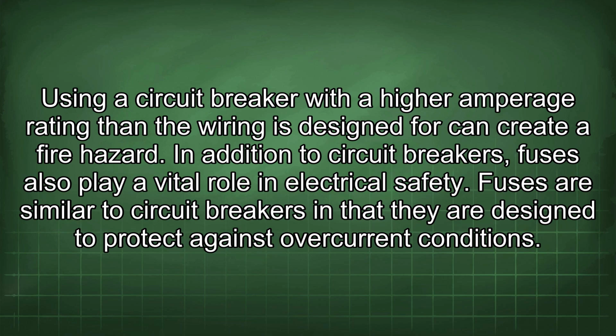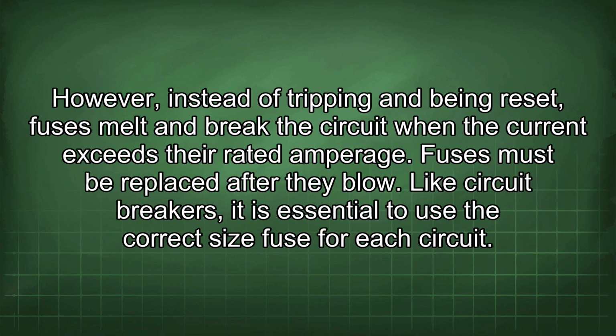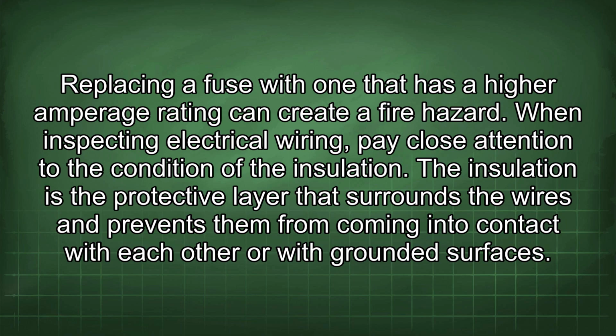In addition to circuit breakers, fuses also play a vital role in electrical safety. Fuses are similar to circuit breakers in that they are designed to protect against overcurrent conditions. However, instead of tripping and being reset, fuses melt and break the circuit when the current exceeds the rated amperage. Fuses must be replaced after they blow. Like circuit breakers, it is essential to use the correct size fuse for each circuit. Replacing a fuse with one that has a higher amperage rating can create a fire hazard.